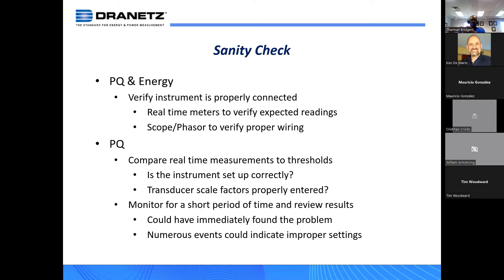Monitor for a short period of time and view the results. Rather than installing the instrument and only returning to retrieve it, it's always a good idea — especially for a longer-term survey — to visit the site periodically. Number one, you may have immediately found the problem. Number two, you may need to make an adjustment to the instrument settings — some tweaking. Those are the primary reasons why I recommend visiting the site periodically to check on the meter.